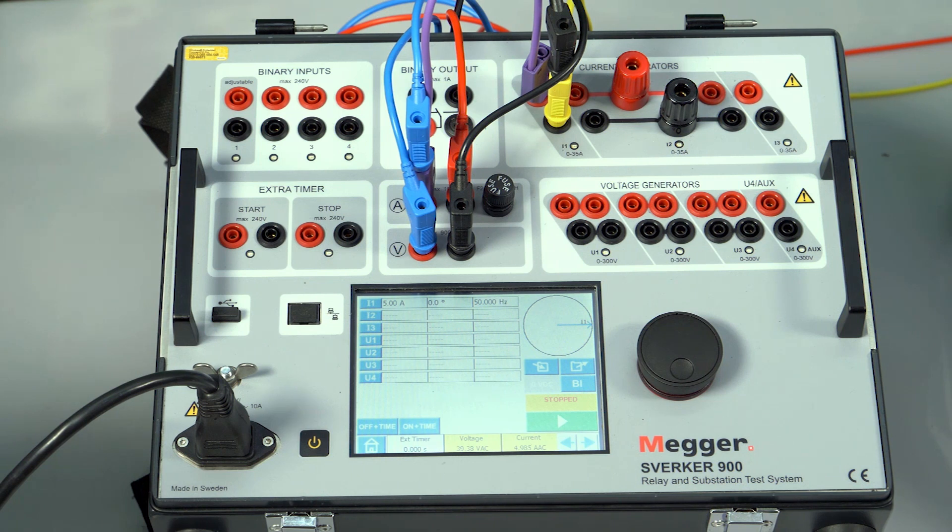The current generators have a burden of 250 VA when operated independently with a compliance voltage of 50 volts. To verify the same, let us connect to 10 ohms resistance and inject 5 amps current.